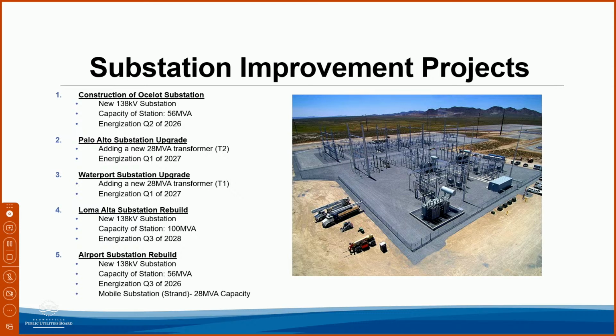We've already gone to the board for approval on purchasing and procuring some of the equipment for the station. We'd ordered about 2 28 MVA transformers, but because of some new opportunities we're seeing, and since we're still in the early design stages of the substation, we plan to go back to the board to procure new transformers with a total capacity of about 100 MVA—2 50 MVA transformers. The reason is that just one load in the port can be anywhere between 50 to 100 megawatts, and we've seen it as high as 300 megawatts. We plan to build that substation in Q3 of 2028.